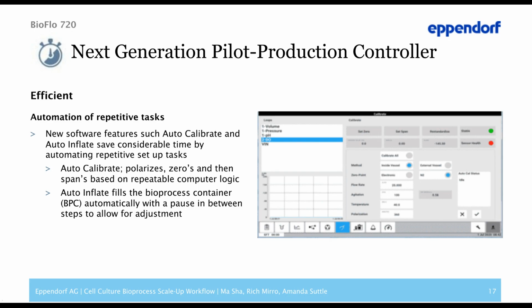Operators may select span or 0 at an individual preference of time. This process automates it and does it the same way every time. The second feature, the auto-inflate, automatically adds gas to the bioprocess container in 2 stages. After the first stage, the bag is inflated approximately 50%. There's a pause. The bag can be adjusted to make sure that the impellers, the sensors, and other critical components are seated properly. Then the process is continued, which fills to 100%, preparing for media to be added.